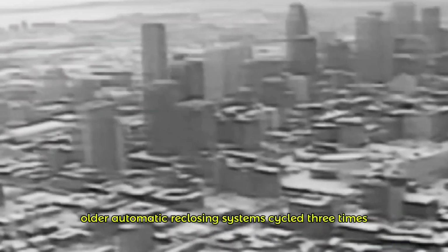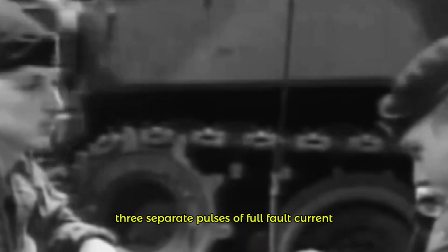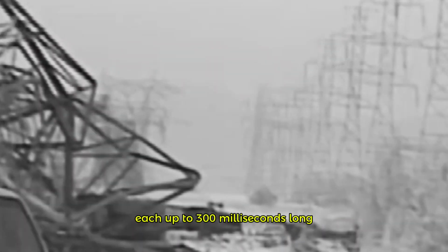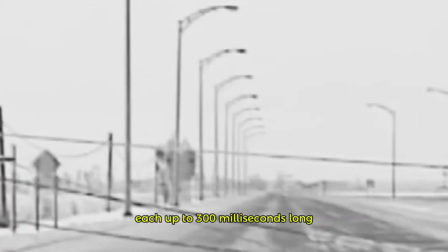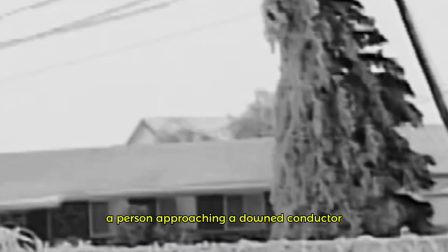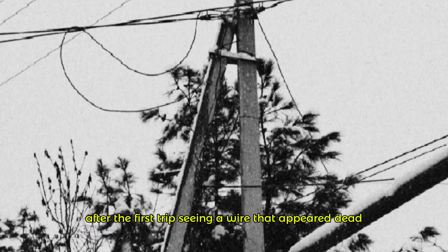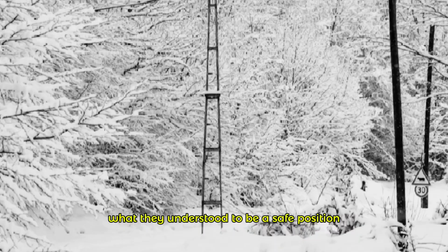Older automatic reclose systems cycled 3 times before locking out permanently, with 15 to 30 seconds between each attempt. 3 separate pulses of full fault current, each up to 300 milliseconds long. A person approaching a downed conductor after the first trip, seeing a wire that appeared dead, hearing no arc, feeling no shock from the ground at the distance where they stopped, could be killed by the second or third pulse while still in what they understood to be a safe position.